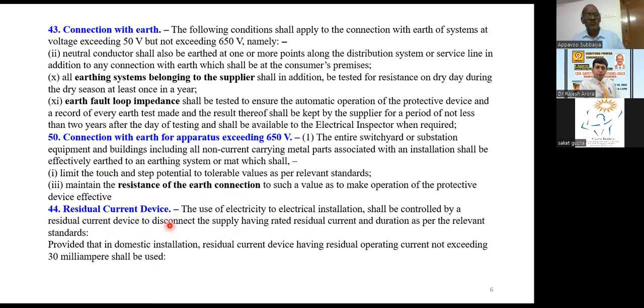But it has become mandatory because we are not confident that we will provide an earthing system with the integrity of achieving the earth fault loop impedance of a TNS system. So we are relying on the residual current device. It is mandatory. Without this device, no service connection will be issued. It has existed for the past several years. Another thing.